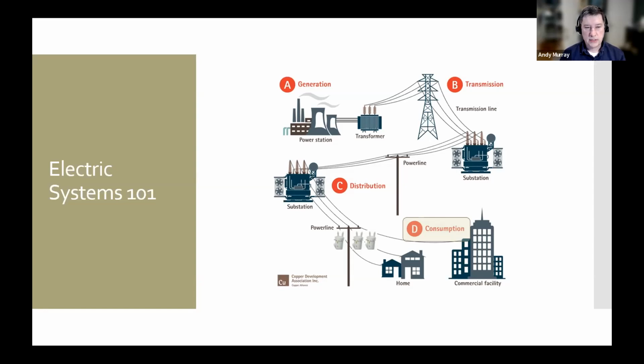In the electric system, those two functionalities are actually separate. You'd have circuit breakers, or distribution reclosers as we sometimes call them. Those devices themselves just do the mechanical opening and closing. You'd have other devices called relays that watch the system and say, okay, I'm seeing more current than I expect, or the voltages seem to be swinging too high and too low, and those make the decision to tell that circuit breaker to open or close.